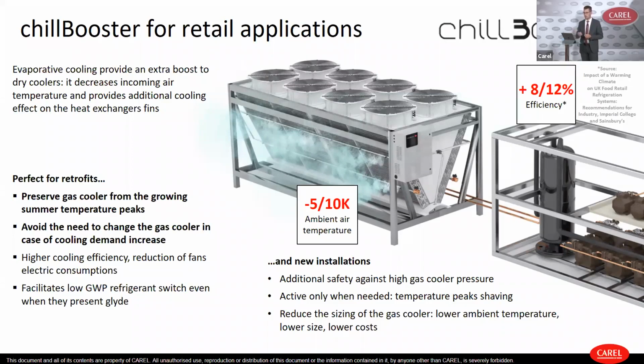What can Chill Booster do to manage this special situation that will be more frequent in the future? If you install Chill Booster, this can shave the temperature peaks. So it is very good for retrofits, where the gas cooler maybe was sized for the temperature of 2-3 years ago or 4-5 years ago that were lower. Now with Chill Booster, you don't need to change the whole gas cooler.